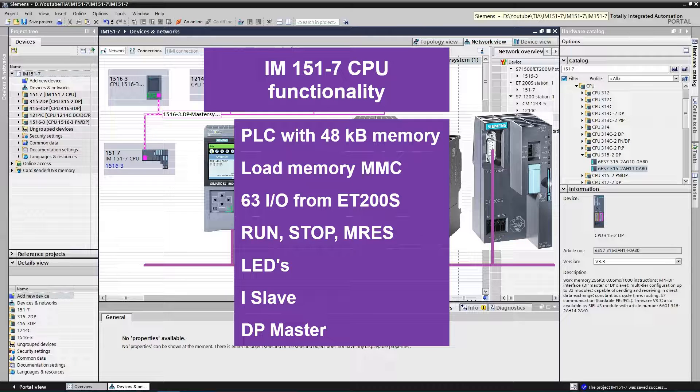Can be connected to the PROFIBUS network. By installing DP master module, you can enable DP master functionality. At the end of the rack, terminating module must be attached, otherwise CPU will remain in STOP mode.